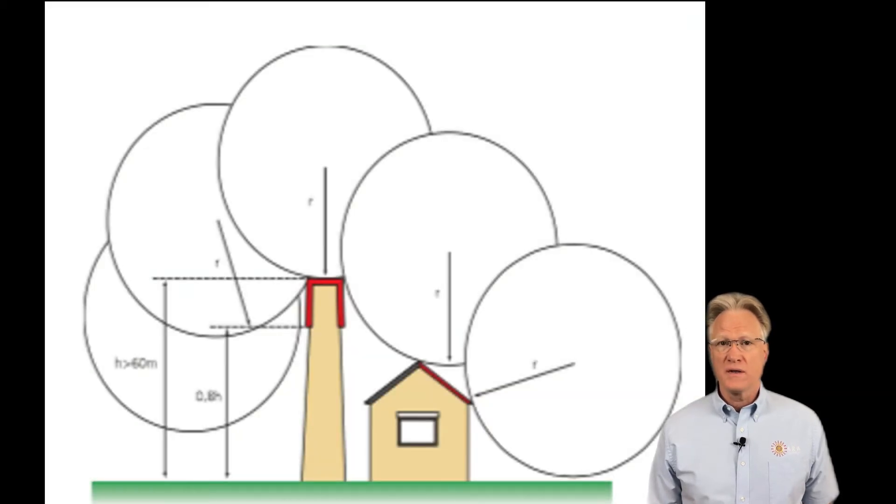I prefer the rolling sphere method. Here is the rolling sphere design method in picture form. The idea is to have the arc of the sphere only touch the lightning rods as you roll it over the structure you're trying to protect. It should always be suspended by the lightning rods and never touch anything you wish to protect.